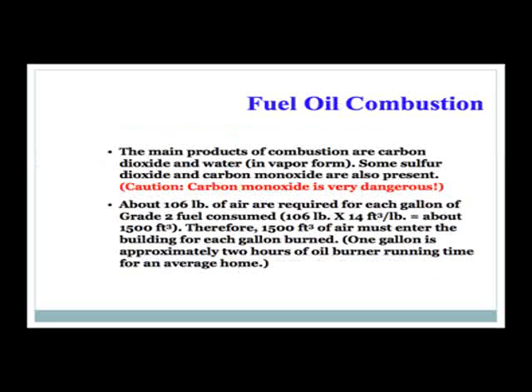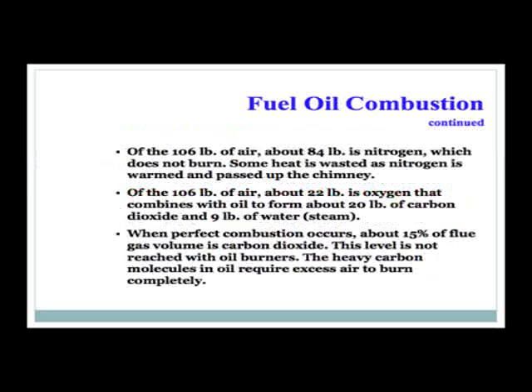About 106 pounds of air are required for each gallon of Grade 2 fuel oil consumed, meaning approximately 1,500 cubic feet of air must enter the building for each gallon burned. One gallon is approximately two hours of oil burner running time for an average home. Out of the 106 pounds of air, some 84 pounds is nitrogen, which does not burn.